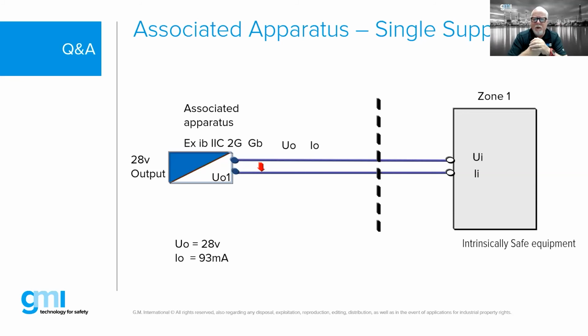So there's entity parameters for the output of the barriers, and there's entity parameters associated with the intrinsically safe apparatus as well. Basically, the transmitter in the field says, I am safe if you provide me no more than say 30 volts, because if you send 380 volts, the thing is going to melt or get too hot. Beside the barrier, there's something that protects the wiring also, so the maximum energy through that barrier will never be sufficient to ignite the mixture of gas present.